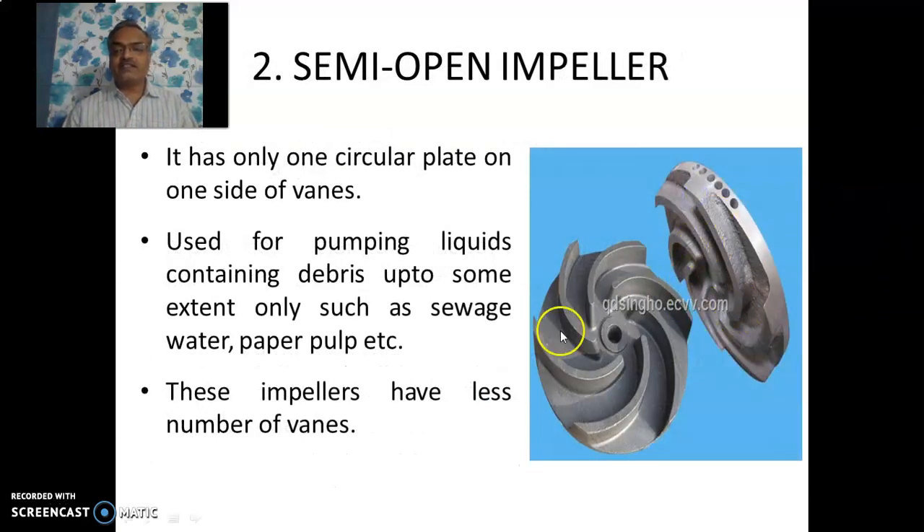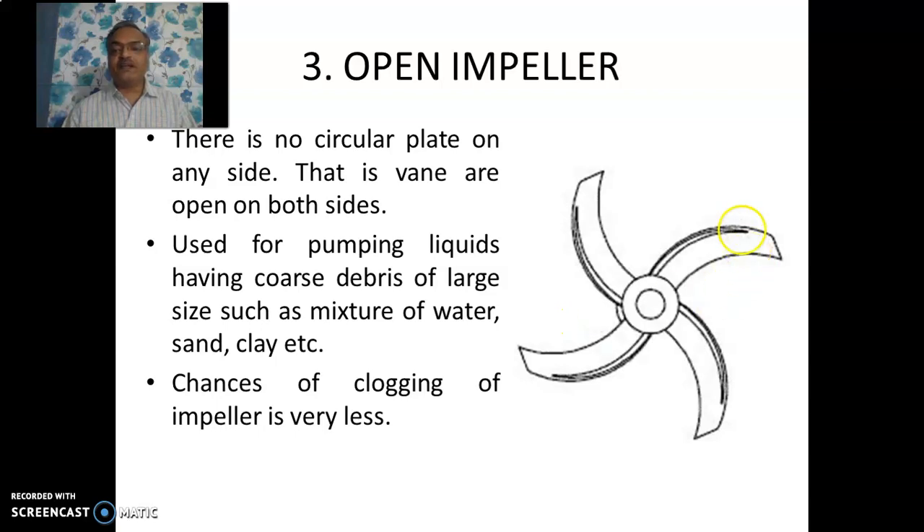Next, the semi-open impeller. As visible in this figure, it has only one plate at the base — the base plate — and the crown plate is absent. So vanes are mounted on only one plate. This type of impeller is used when the liquid to be pumped contains some amount of debris or foreign particles such as sewage water, or paper pulp. These impellers have fewer vanes. The third type is the open impeller, which has only vanes or blades — no base plate, no crown plate. This kind of impeller is used when the water to be pumped contains a large amount of debris or coarse particles, for example a mixture of water and sand or clay. The absence of both plates reduces the chances of blocking.